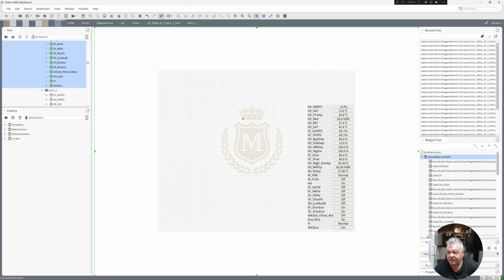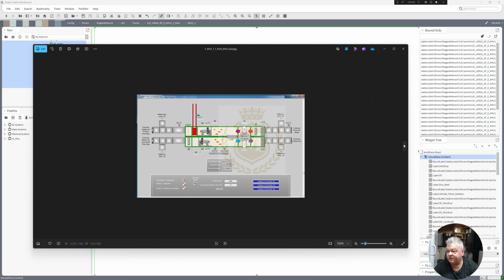So I need to look at this AHU1. Let me put you on pause. I've got a snapshot somewhere of it. So here's my snapshot that I've got from the Desigo system, the Siemens Desigo. We've got a heat exchanger that they're using there. They've got a bypass damper here. Filter, filter, fan, fan, heating coil, ducting.